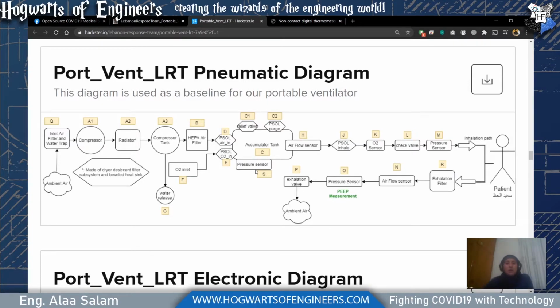Another thing we need is an airflow sensor, which is identified as entity H. The airflow sensor in this position will see if the flow of the oxygen-enriched air going into the patient's lung is set at the level that we specified. Because when you are setting the properties of the ventilator, one of the properties you have to control will be the volume and the time and the flow, or the pressure and the time and the flow. From those, if you set the volume, you will calculate the pressure, and if you set the pressure, you will calculate the volume.